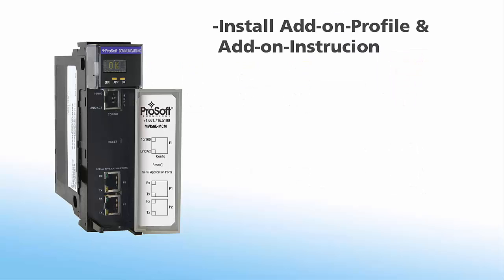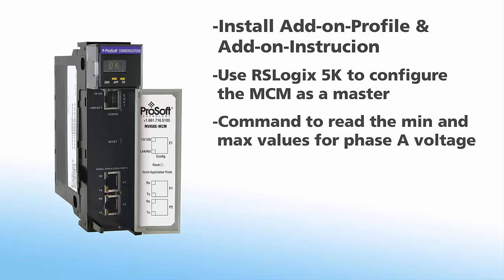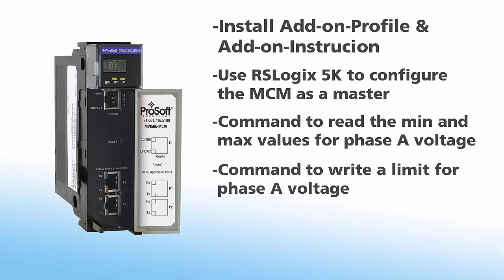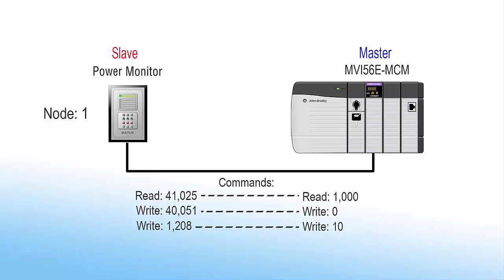In this video we'll install the add-on profile and add-on instruction for the MCM. We'll go through the process to configure the MCM as a Modbus master and then set up master commands to talk to a power monitor. We'll create a command to read the minimum and maximum levels for phase A voltage, write a voltage limit for phase A, then write some bits to reset the minimum and maximum voltage for phase A. This is the node of the power monitor I'll be working with and the addresses that I'll be using.